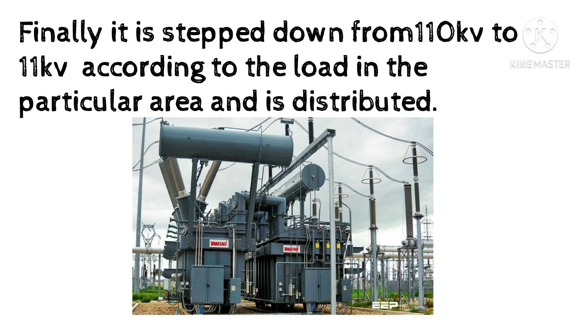This is called a step down. So it was stepped down from 440 kV to 220 kV. Then the 220 kV electricity is transferred to another substation where it is stepped down to 110 kV. From this substation, finally the electricity is transferred to another substation which has 110 kV electricity, which is stepped down again to 11 kV and is distributed according to the load in the particular area.